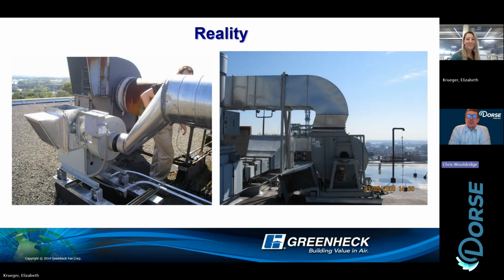And I think I saw somebody comment, Sam. Yeah, thanks for mentioning that, Sam. So Greenheck does have a live system effect demo. It's probably one of the more impactful things. And Sam heard me say this: that's a demo that has nothing to do with Greenheck. That is just fan physics. It applies to every fan manufacturer. We take a small utility set fan and we put on different duct connections. We show some that are how AMCA tests the fan, so you can see a baseline performance. And then we put on really, really bad duct connections, but really common things you see in the field.